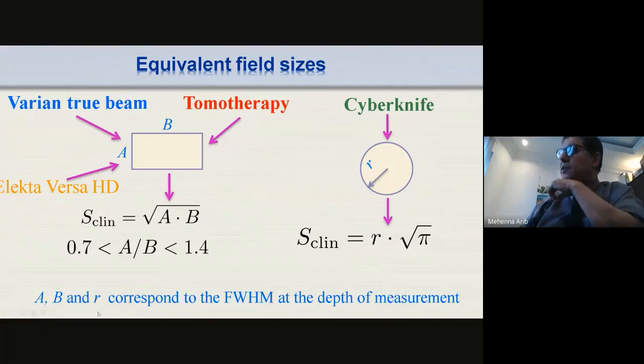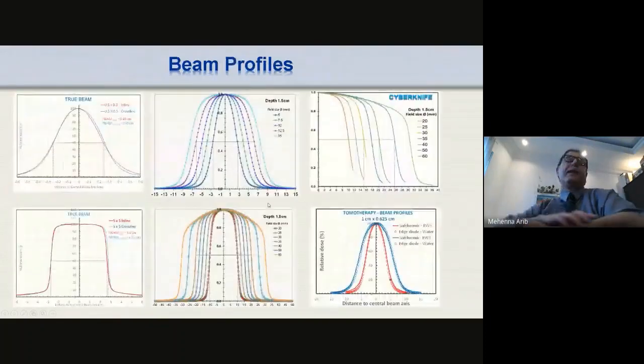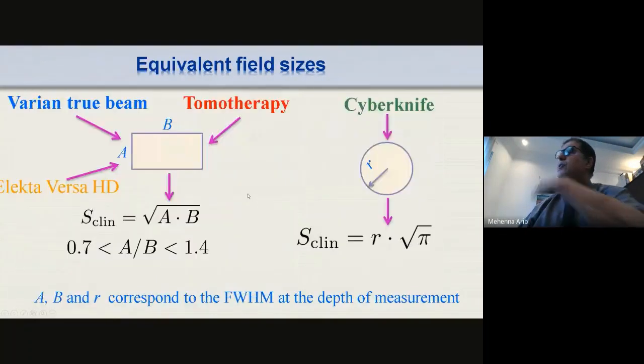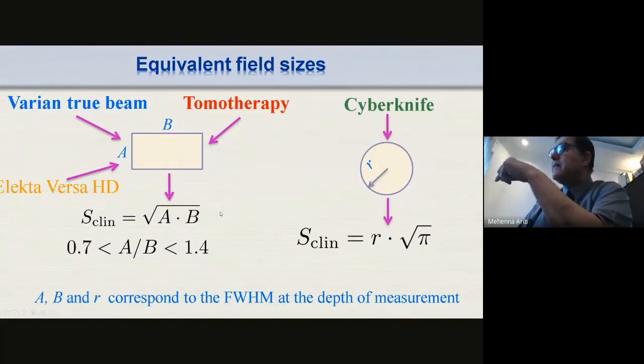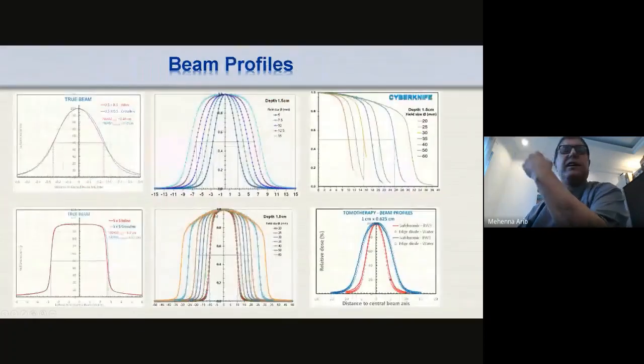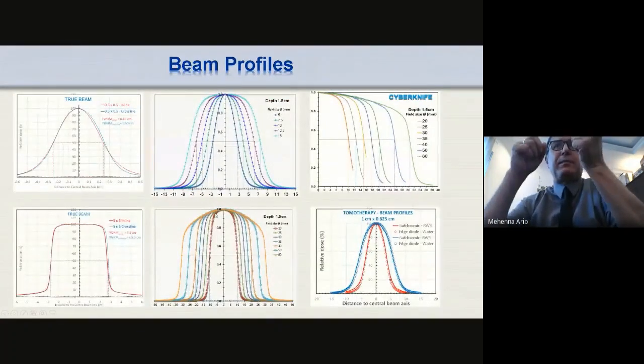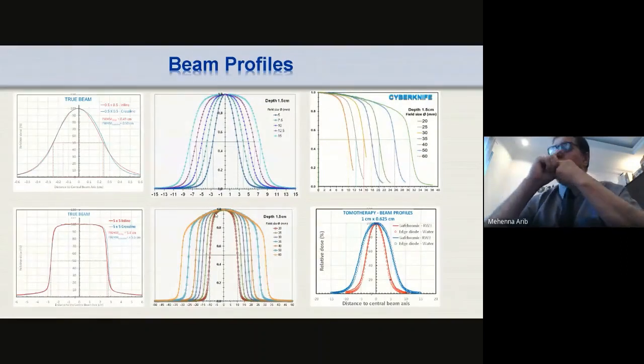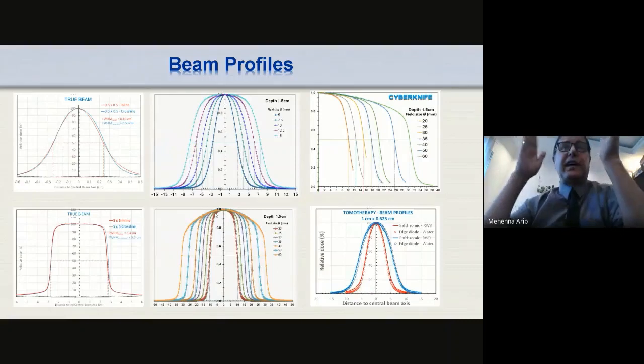Okay, and the condition is that A over B should be between 0.7 and 1.4. For the Cyberknife, it's given by R times the square root of pi. So you have to convert your field size to the equivalent field size and use it for the tables. Okay, but to calculate A and B, you need to calculate the full width at half maximum to use it for calculating the condition for the chamber and also for the actual field sizes.